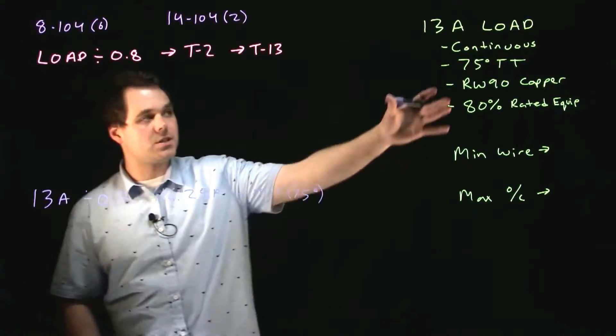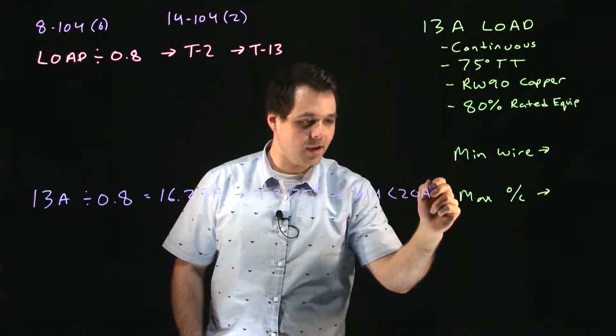16.25 amps. I take that to table 2. This will be my minimum ampacity of my conductor. I'm going to use the 75 degree column. I'm using 75 degree column because that's what all my temperature equipment is. It gives me a number 14 which is said is good for 20 amps.